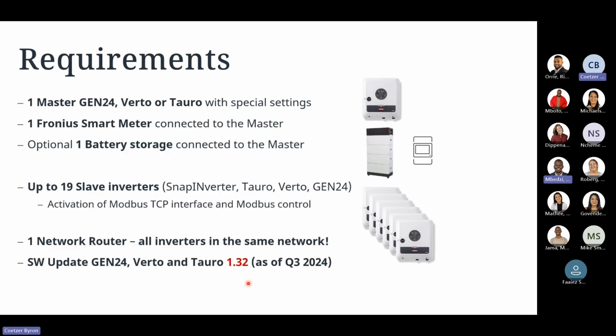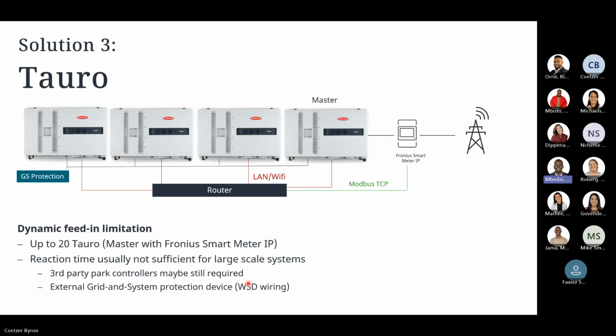Byron: Yes, just on that question, is it because of the Fronius smart meter, or what causes that you need a third party device? It's the Fronius smart meter itself. Okay. So the settling down of the inverters is still fast enough. Yeah, the ramp down is, but it's due to the communication directly from the smart meter. It's not quick enough. So okay, I see, that's why. We recommend having that meter control in place to make sure that we then obtain that correct reaction time. Okay, perfect. Thanks for that.